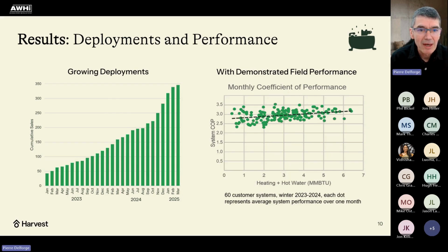So in terms of results, as of last month we were up to nearly 350 systems sold, and the results in the field speak for themselves. The little chart on the right shows every dot as an average COP over 1 month for one system. It's really right around 3.0, more or less, depending on how much heat and hot water people use and the relative impact of thermal losses, which on average are around 5%.